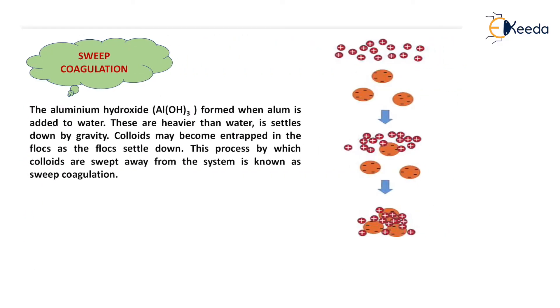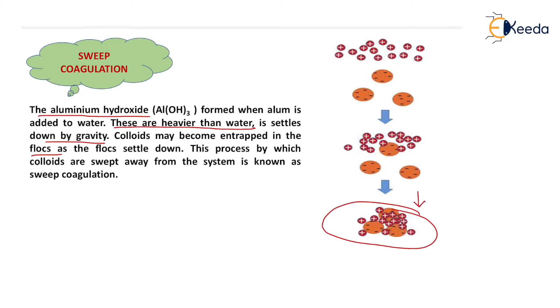The next mechanism is sweep coagulation. The aluminium hydroxide which is formed when coagulant alum is added in water is heavier than water and settles by gravity. When we add alum in the water it forms a sticky gelatinous substance. When this sticky gelatinous substance comes in contact with colloids, it creates charge neutralization. When charge neutralization takes place, all the particles come in contact with each other, grow in size, and settle down at the bottom of the tank. This is known as floc formation and the settlement is known as floc settlement. In this process all the colloids are swept away from the system, that is why it is known as sweep coagulation.